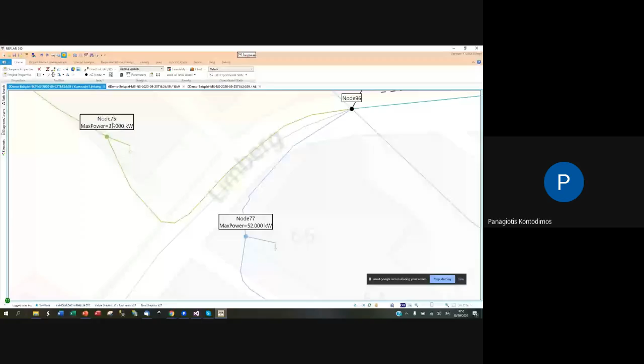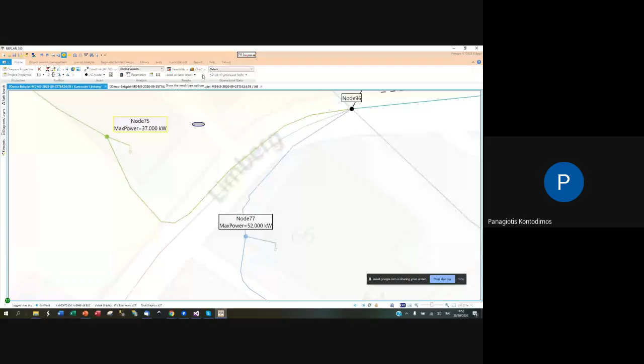I could also see for each individual location how much power I can connect. I go to connection point power, make this calculation, and it tells me that at this certain location you can connect a maximum of 37 kilowatts, no more, because if you connect more you will have a problem.